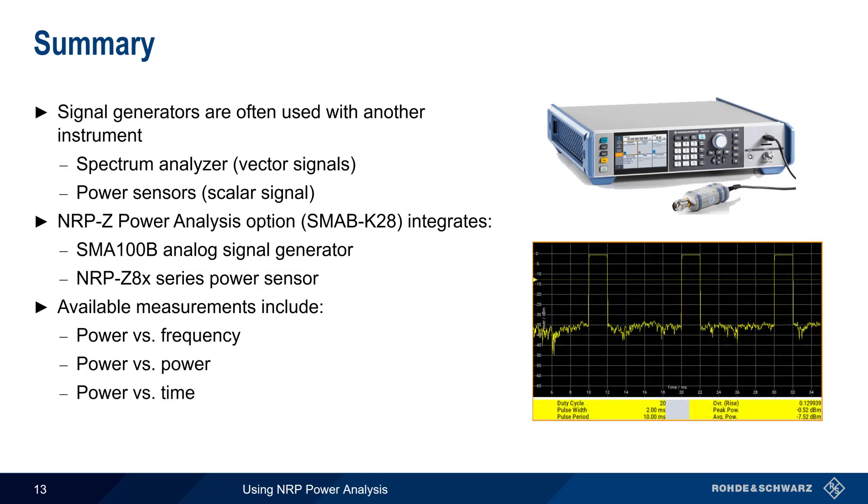So in summary, signal generators are often used with another instrument that measures how a device under test changes a signal. Spectrum analyzers are needed for the measurement of vector signals, such as LTE, 5GNR, or Wi-Fi, whereas power sensors can be used for scalar measurements of received power. The NRP-Z Power Analysis option integrates an SMA100B analog signal generator and NRP-Z8X series power sensors into an efficient, low-cost way of making scalar measurements. These measurements include power versus frequency, such as measuring a filter's passband, power versus power, such as measuring an amplifier's gain and compression point, and power versus time, such as measuring the parameters of a pulse signal.